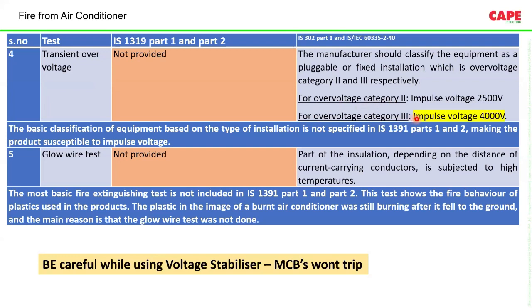That means the air conditioner must be tested with an impulse voltage of 4 kV. So an air conditioner tested as per IS 302 coming under impulse voltage category 3 is the best solution. Similarly, for example, IS 1319 is not talking about the glow wire test, whereas IS 302 talks about the glow wire test. So you must be careful while buying new air conditioners.